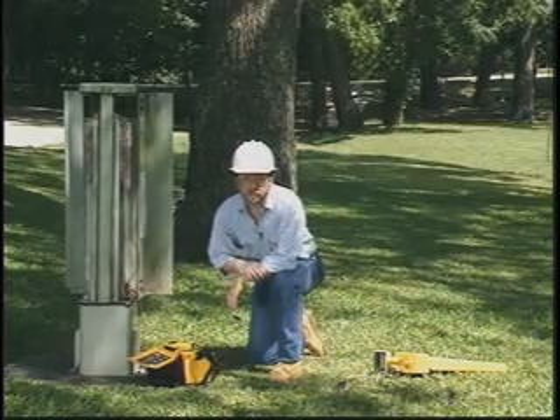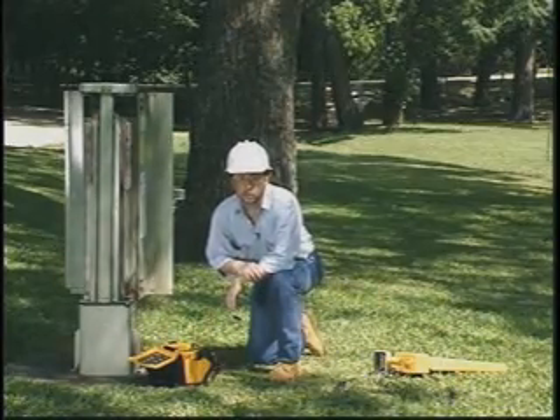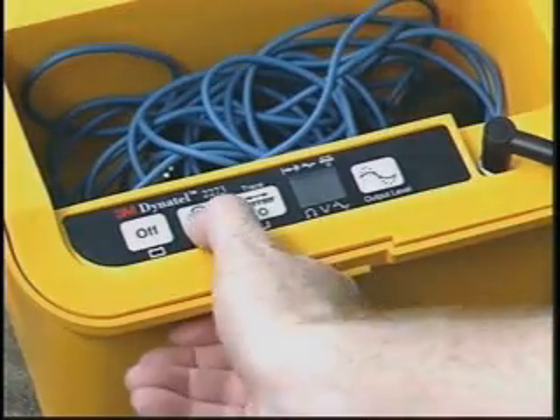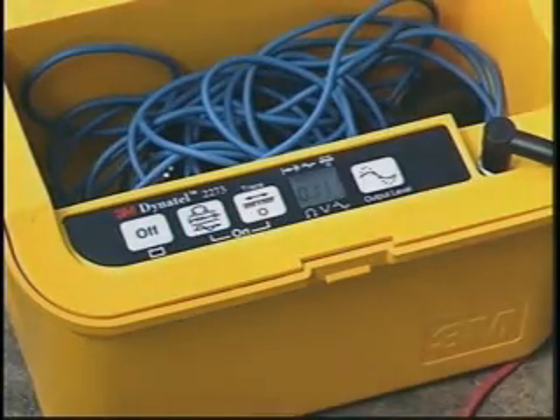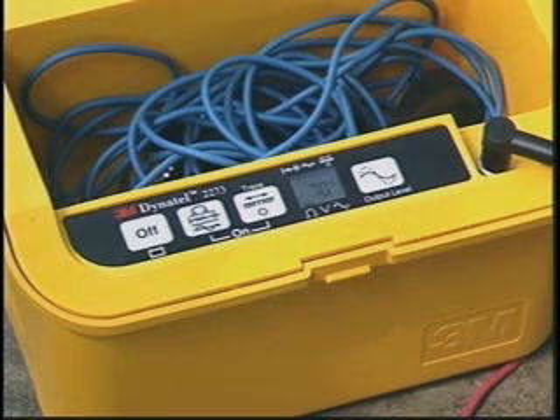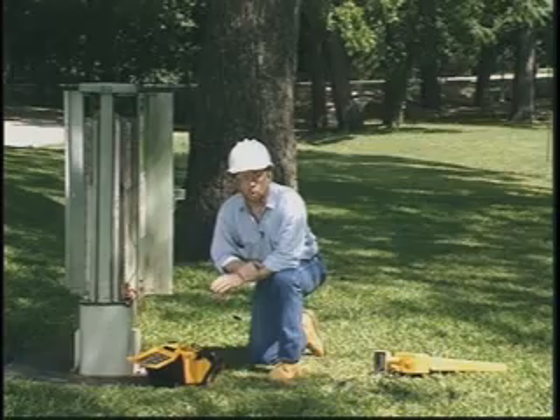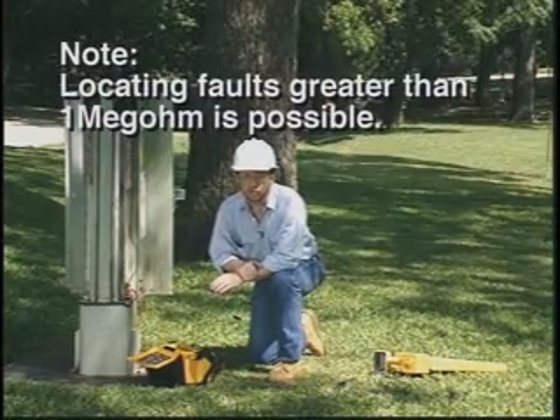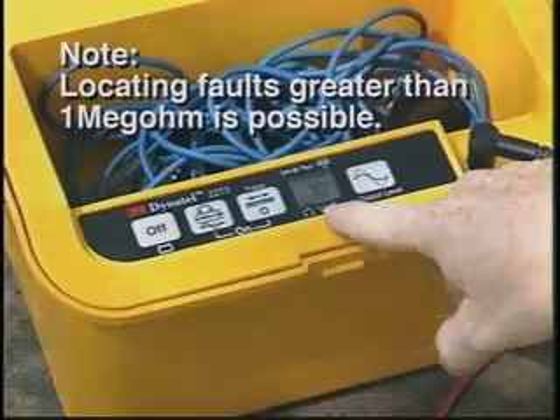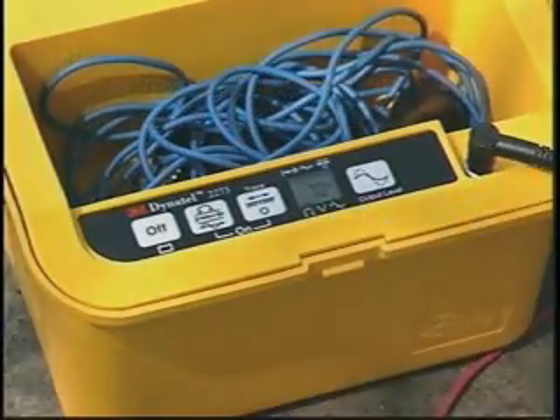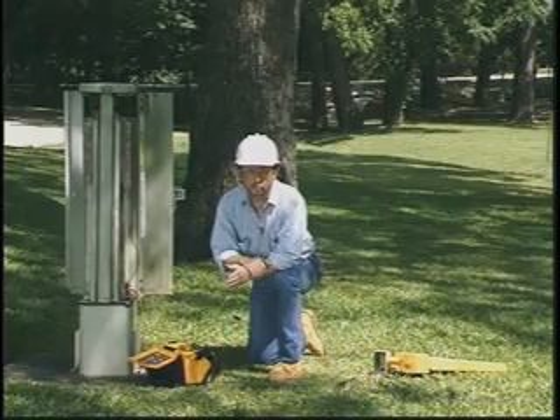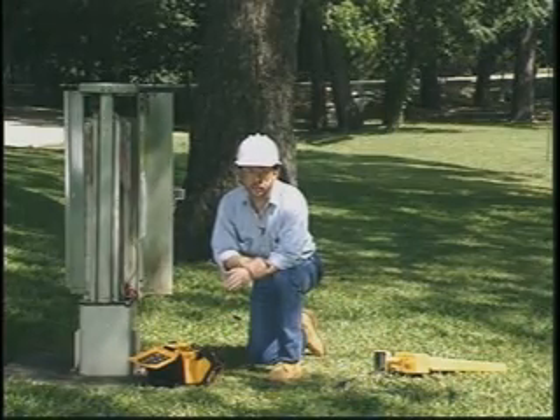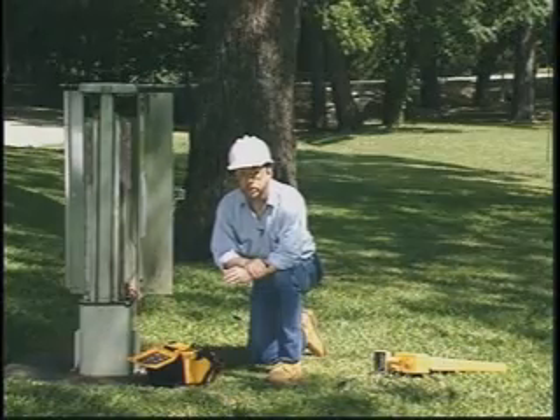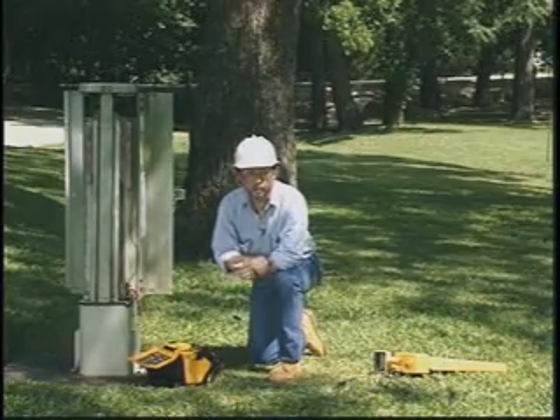To verify the fault resistance and to check for foreign voltage, turn the transmitter on by pressing the ohms key. If foreign voltage is on the line, the display will alternate to show voltage and resistance. In this case, there is no foreign voltage, so it only displays resistance. If the resistance is more than 1 megohm, there is no significant fault on the section. Between 1 megohm and 50,000 ohms indicates a high resistance fault. It may not be causing problems yet, but most likely it will get worse with time. Less than 50,000 ohms indicates a heavy fault between the shield and earth.